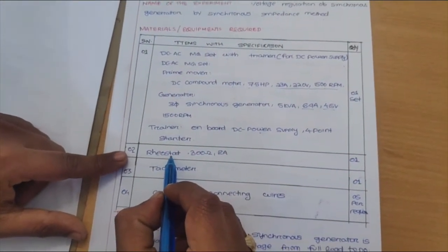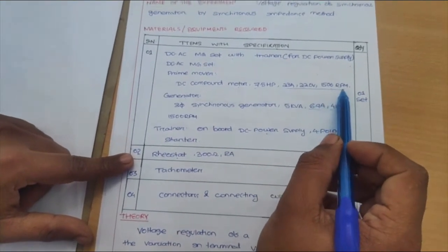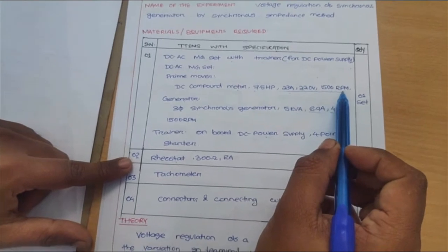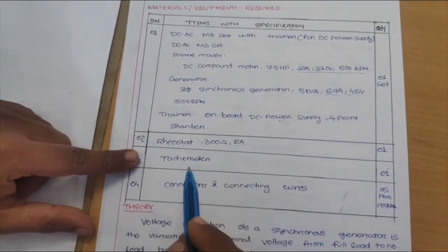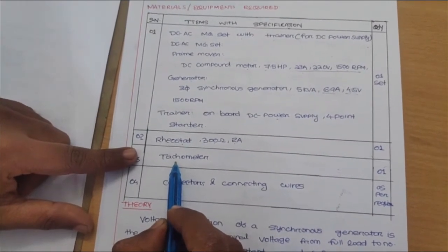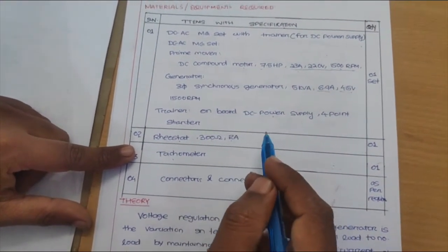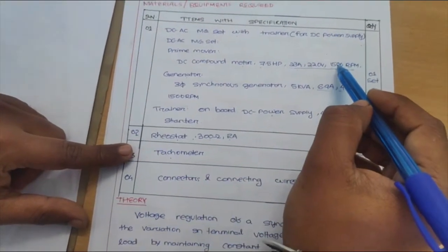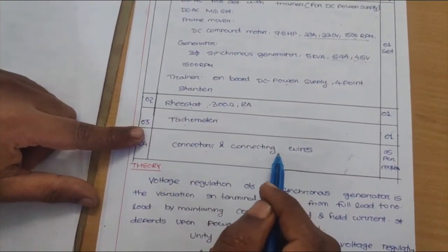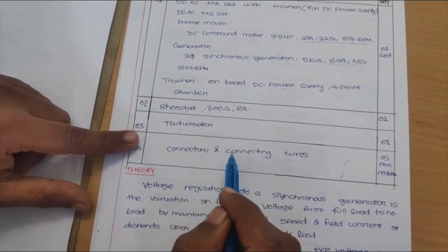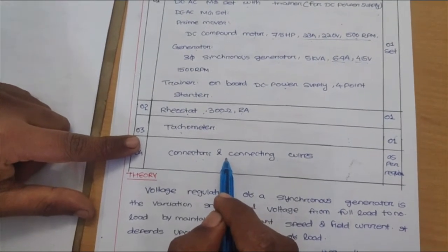Next, we require a rheostat to control the speed of this motor by the flux control method. While doing this practical, you have to maintain the speed constant. A rheostat of 300 ohms is required to change the speed of the prime mover by the flux controlling method. A tachometer is required to measure whether we achieve the rated speed or not. If speed decreases, we need to increase the resistance of the rheostat; if we need to decrease the speed, we decrease the resistance of the rheostat. Connectors and connecting wires are required for short-circuiting the terminals of the synchronous generator while doing the short circuit test and the OC test, and for making the connections.